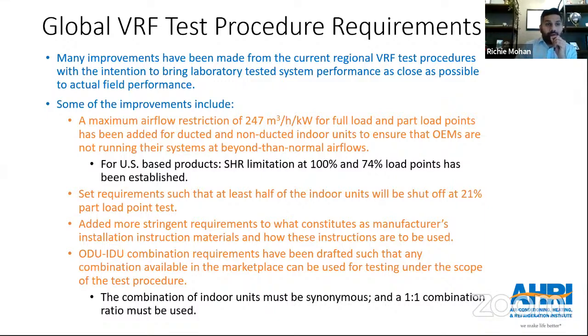This will significantly reduce any potential gamification which could be done, any potential loopholes which could exist. It's basically opening the entire standard up to thousands and thousands of combinations which could potentially exist in the field between outdoor unit as well as indoor unit. Now, of course, from a manufacturer standpoint as well as a design engineer standpoint, that just sounds way too cumbersome. But we have added in certain provisions in the global standard such that the use of modeling tools, simulation tools, which is basically what manufacturers are doing today to some extent.